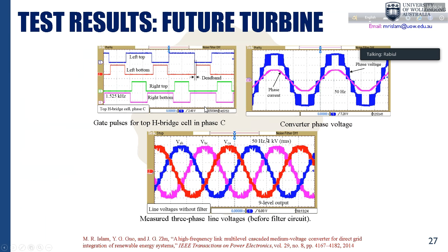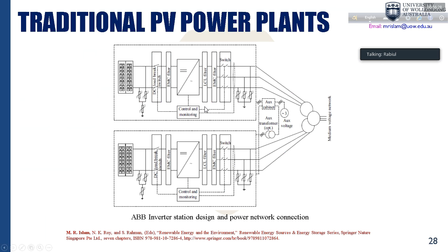If we look at traditional PV power plants, what technologies are industries proposing? The concept is still using a two-level inverter, and this two-level inverter has higher harmonic components, so they need a filter circuit—a heavy LCL filter—and also the switching frequency here is much higher.